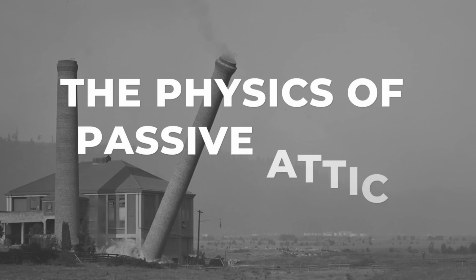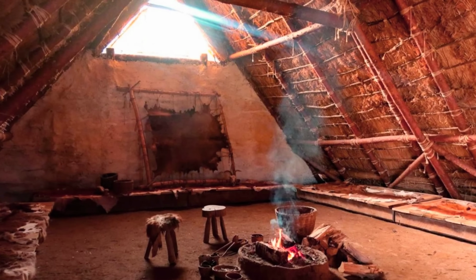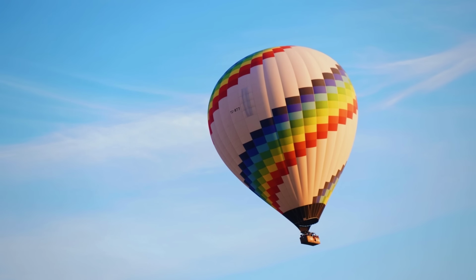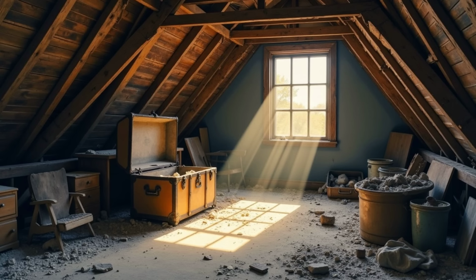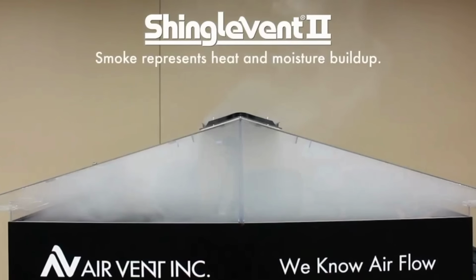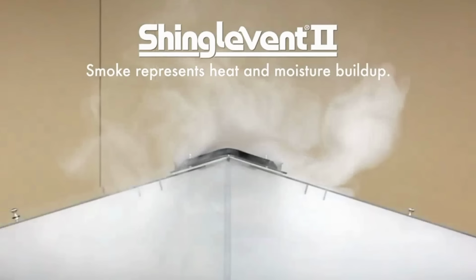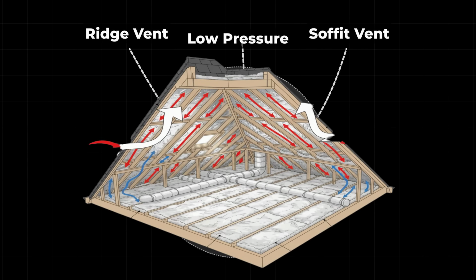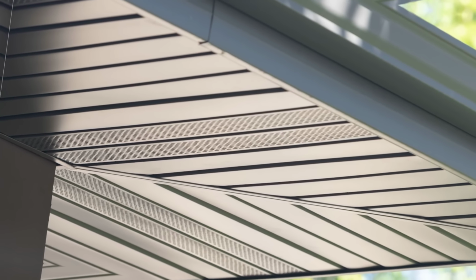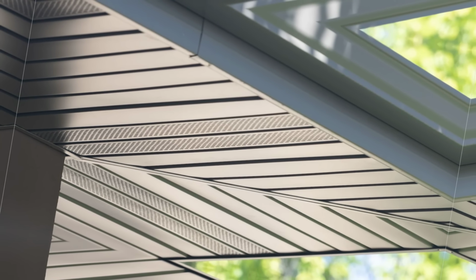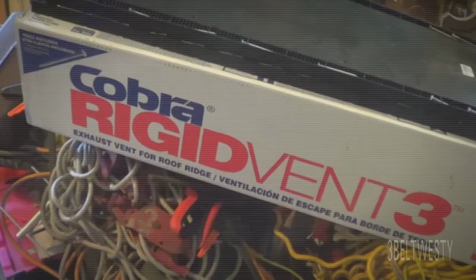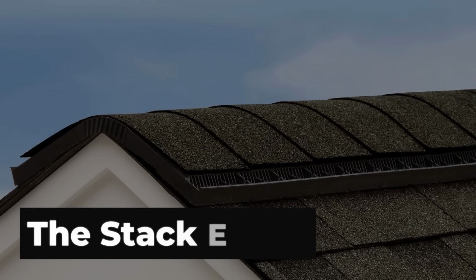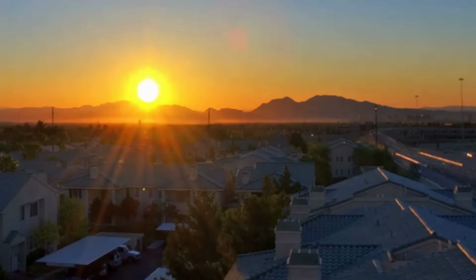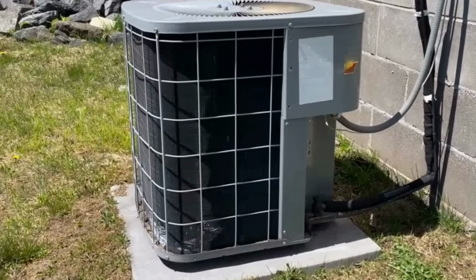The physics behind this mesh is older than every modern building material combined. It is called the stack effect, and it has been moving air through structures since humanity first built enclosed spaces. Hot air is less dense than cold air, and less dense air rises. When superheated attic air sitting at 150 degrees on a summer afternoon has a path to exit at the highest point of the roof, it rises and escapes. As it exits, it creates a zone of lower pressure inside the attic. Cooler outside air, drawn in along the roofline at lower elevation, fills that pressure gap. That incoming air is then heated, rises, and exits again in a continuous loop. Entirely passive and entirely free, it runs every minute the sun heats the roof, which is exactly every minute your air conditioning is fighting its hardest battle.